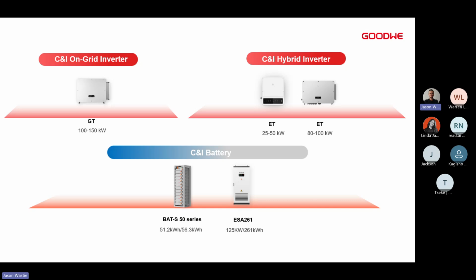So we actually have three batteries, with the BAT S 50 forthcoming soon, which is a 56 kilowatt hour battery solution. We have the BAT 100, which is in between the two, a 100 kilowatt hour battery, all in one battery cabinet. And then the 125 kilowatt, 261 kilowatt hour PCS solution that we will be discussing as well. Coming soon on top of this, we have a 200 kilowatt hour battery as well as a 125 kilowatt inverter.